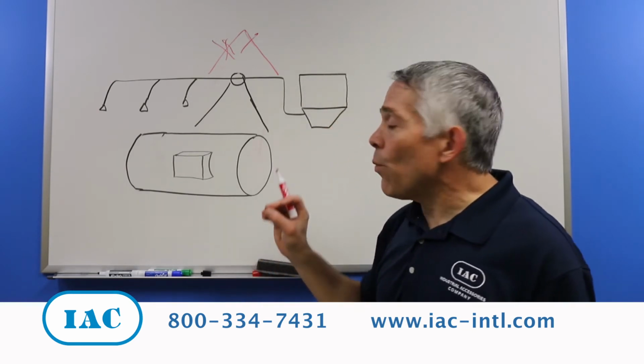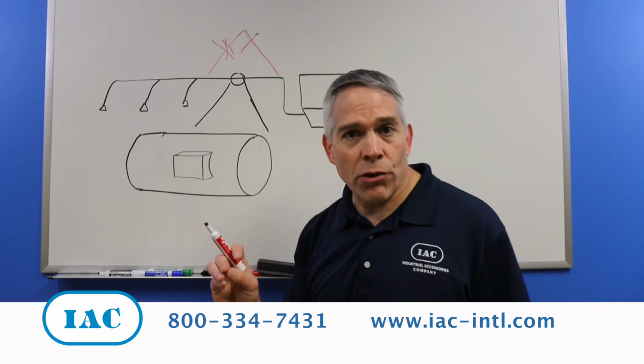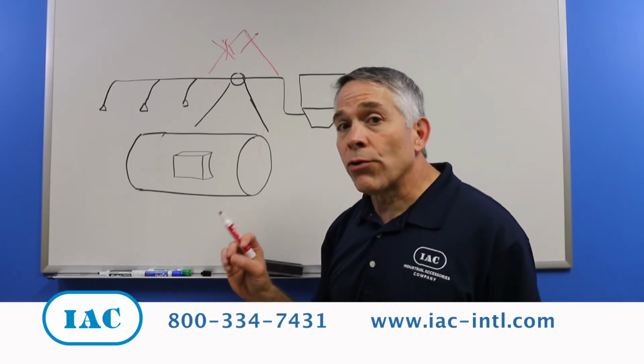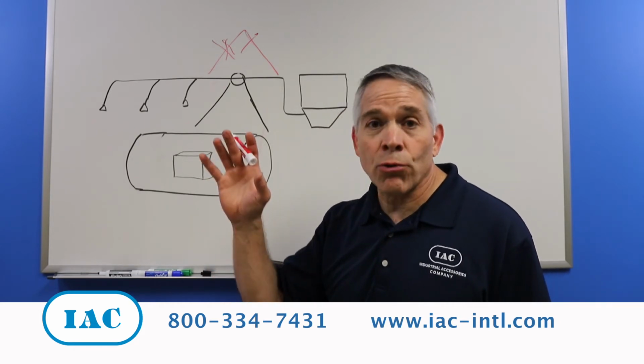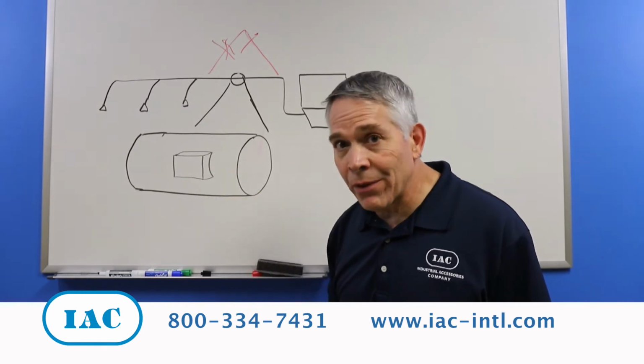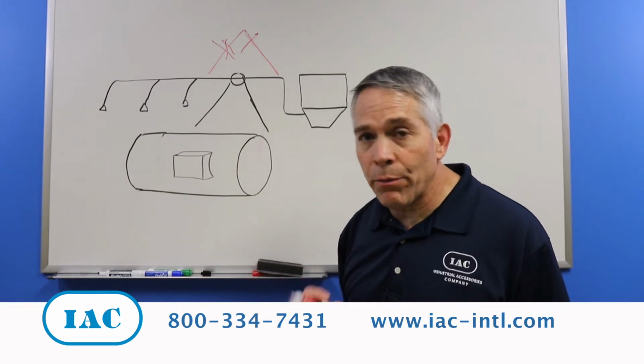Now, to do that, we strongly recommend putting inspection doors to avoid material accumulation, because there have been cases where ductwork collapses, sometimes bringing part of the building down. It's not only a hazard, but it's an expensive problem.